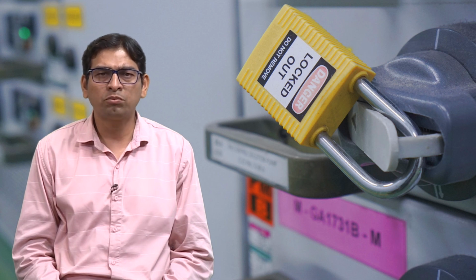Some equipment may require you to remove fuses. In these cases, it is not enough to just pull the fuse out of the box. The box must also be locked and tagged. If you find that you cannot use standard lockout devices on a fuse box, consult your supervisor. If there is more than one source of electric power to a machine, it may be easier or necessary to lock out a main panel.